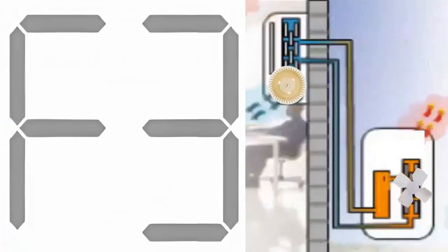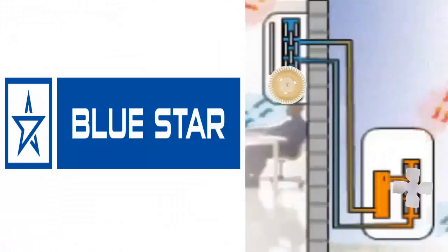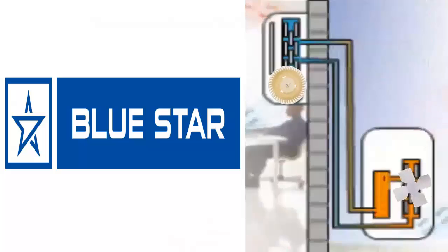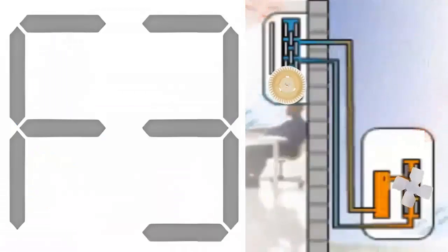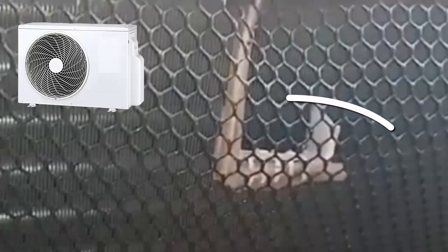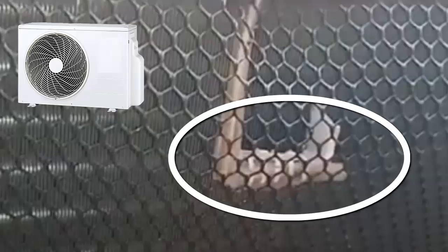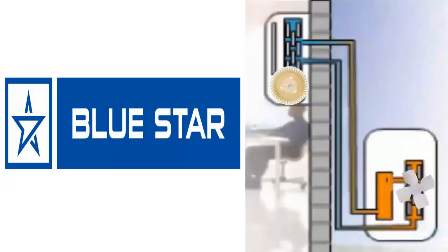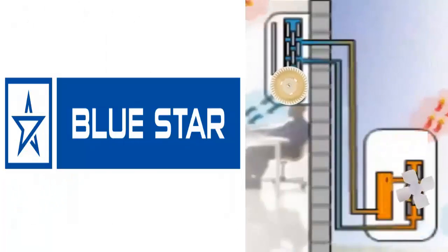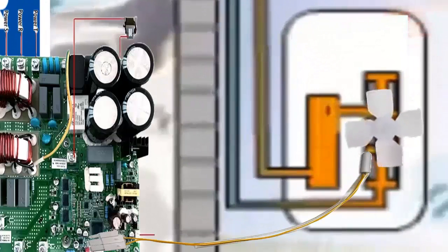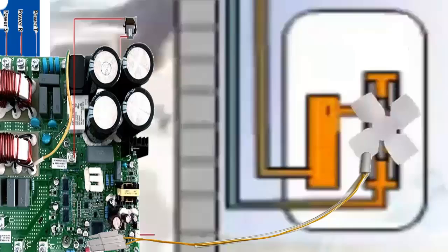Code F3 indicates a problem with the outdoor ambient temperature sensor located in the outdoor unit. This sensor measures the temperature of the air that the outdoor fan sucks in to average the temperature of the outdoor environment. Code F4 indicates a problem with the outdoor unit coil temperature sensor, which measures the refrigerant temperature inside the coil to calculate the refrigerant saturation pressure.